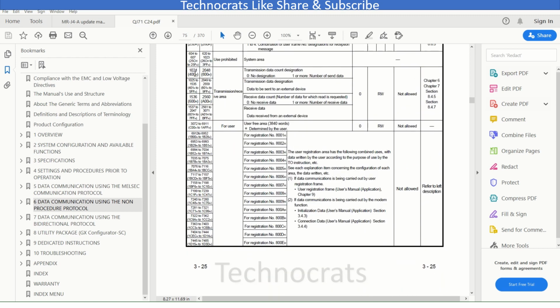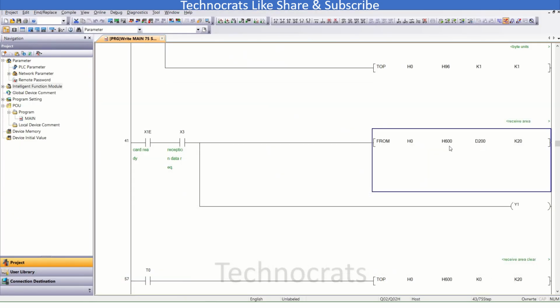So 600, okay. This is 600 for channel number 1, that is receive data count. So in this case, when you receive the data, suppose the length is 8, it will show 8. And 601, you can see 601 is here. From 601 you will receive the data, which is the data which you want. So U0\G600 will move to D200, and 601 to 619 will move to D201 to D219. So basically from D201 you will receive the data.